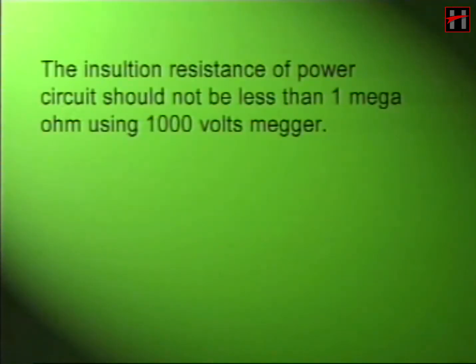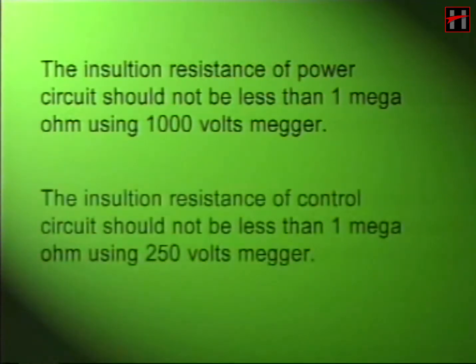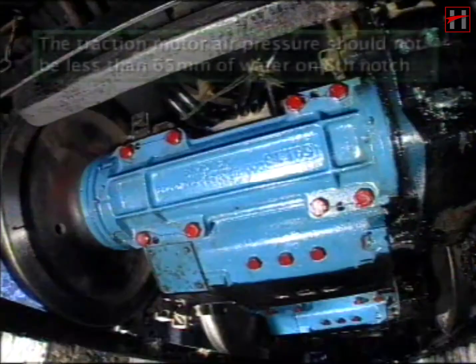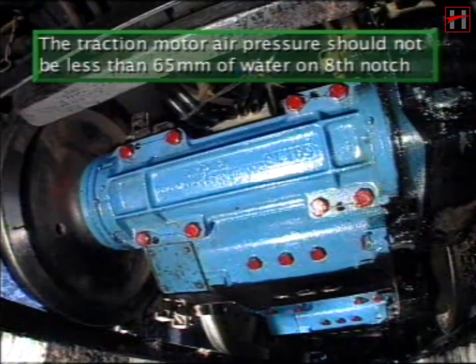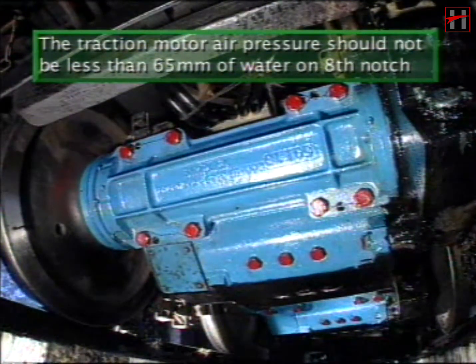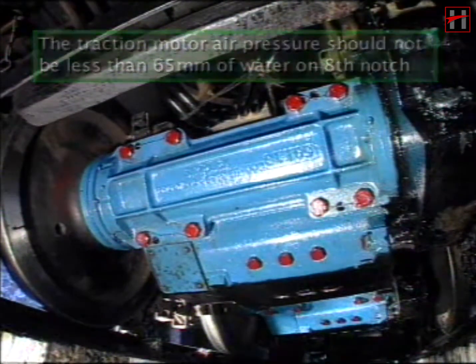The insulation resistance of the power circuit should not be less than 1 mega ohm using a 1000 volt megger. The insulation resistance of the control circuit should not be less than 1 mega ohm using a 250 volt megger. The traction motor air pressure should not be less than 65 millimeters of water on the 8th notch.